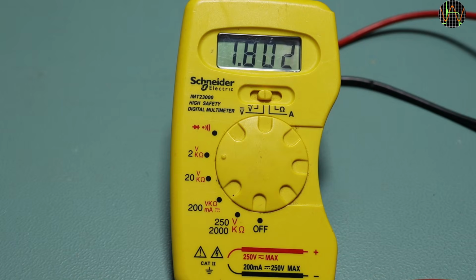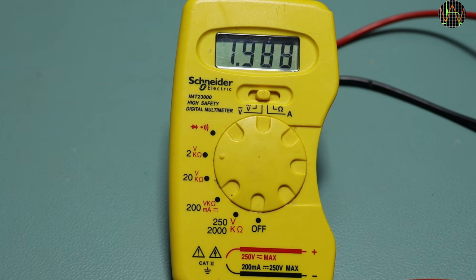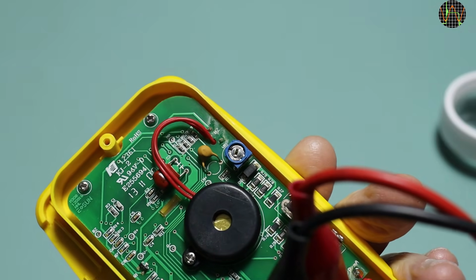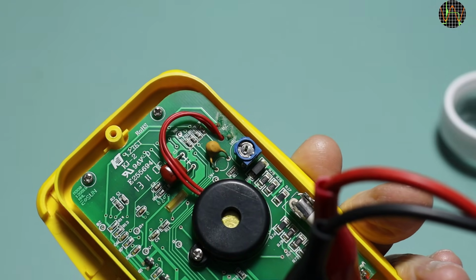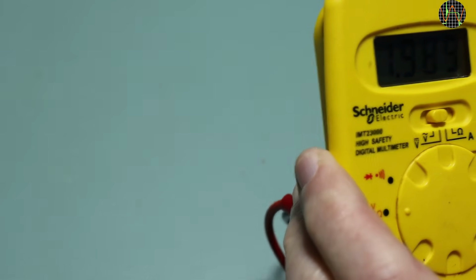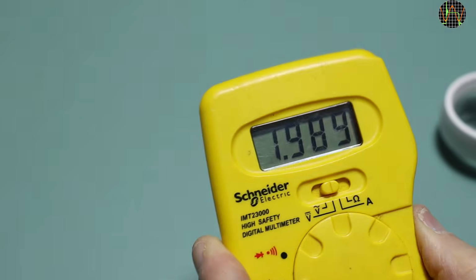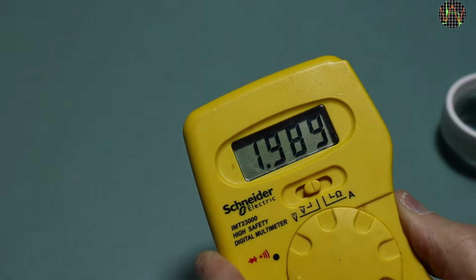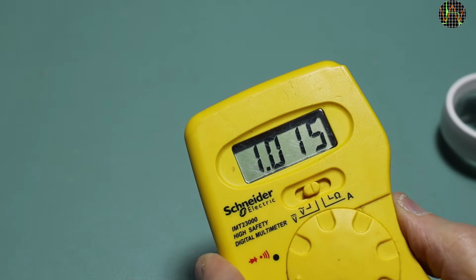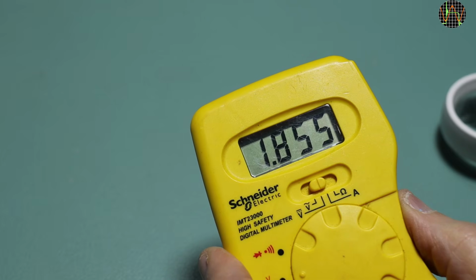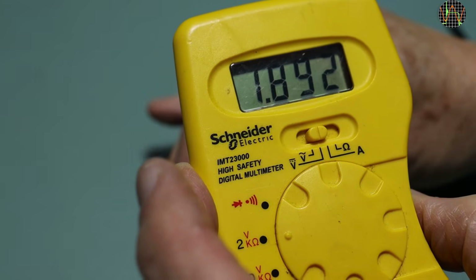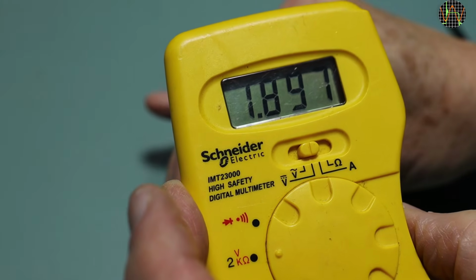With 2 volts it shows 1.989, so I think I should try recalibrating it. There is, after all, just one trim pot, similar to many old Fluke meters, and those are calibrated by simply applying a known DC voltage and changing the trim pot until the meter reads the correct voltage. That cal is then used for all other ranges. I assume this meter does the same. Instead of 2 volts, I pick 1.9 volts since the maximum display is 1.999. Changing the pot until the meter reads 1.900.